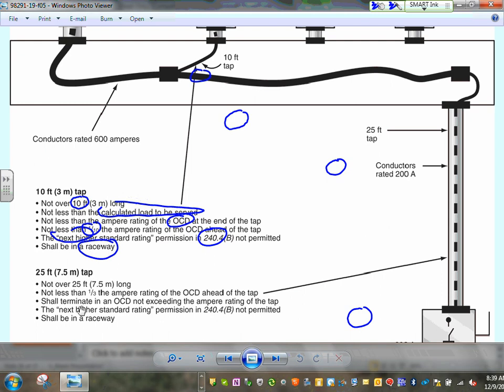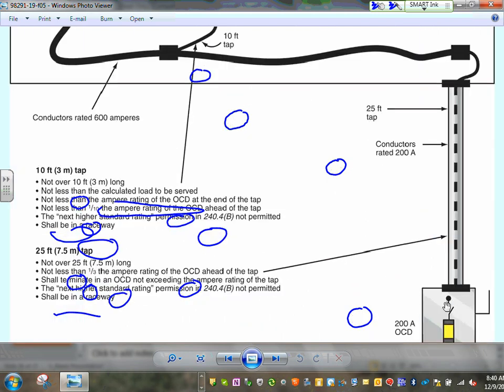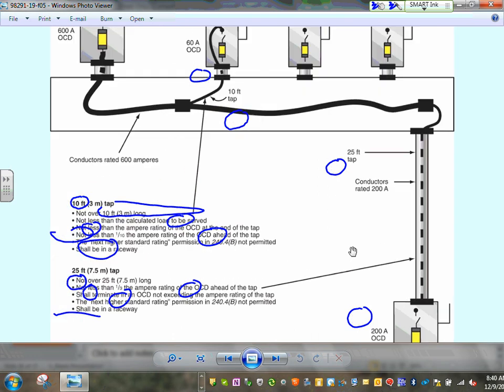Very simple. If you look at the one underneath it, the 25 feet, it's the same thing. It's no more than 25 feet, 1/3 of the overcurrent device. It has to be rated, it has to land on an overcurrent device. You can't go to the next standard, and you have to put them in a raceway. I'm going to use the 25-foot rule here, guys, and show you how they do this calculation.